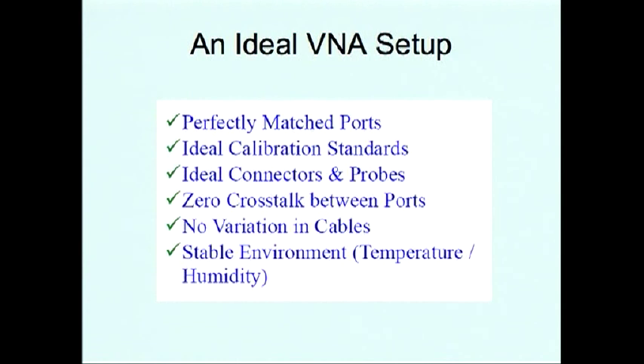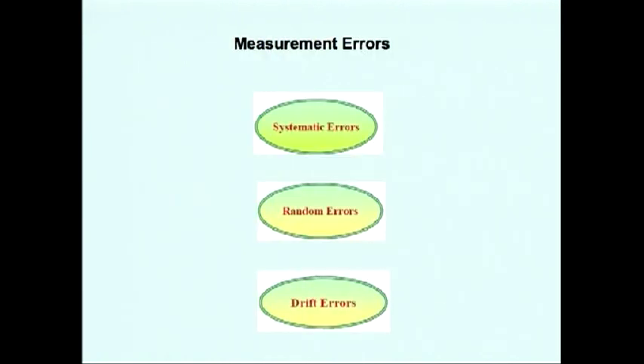An ideal vector network analyzer setup would have perfectly matched ports, ideal calibration standards, ideal connectors and probes, zero crosstalk between ports, no variation in cables, and will have a stable environment. However, practically speaking, there are always some kinds of errors that develop while conducting measurements. There are three different types of measurement errors: systematic errors, random errors, and drift errors.